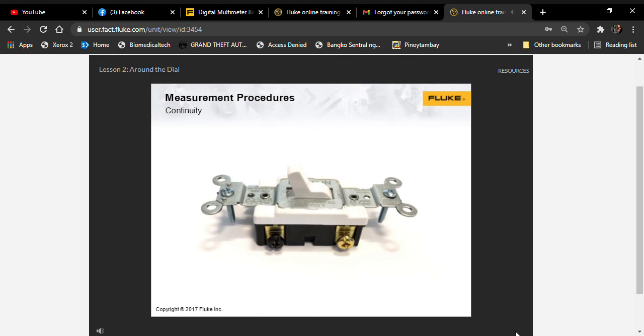Continuity is used to test a circuit for a low resistance path and ensure that connections and splices are good. Also, continuity is used to check switches to see if they're working properly or to identify the terminals. While the multimeter is connected to two terminals, the switch is operated back and forth to determine which position has continuity.